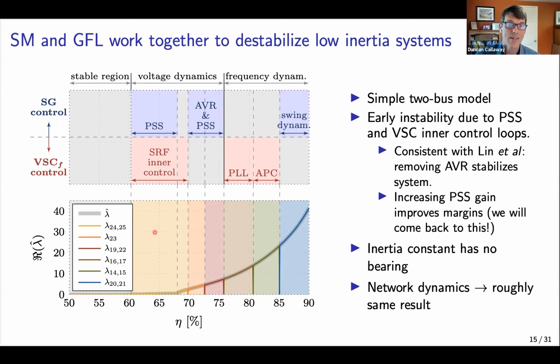What's interesting here is to ask what dynamics are implicated in this destabilization event. Looking at the largest participation factors in our instability, this is a quantitative way of saying which state variables play the biggest role as it evolves. You can see it's the power system stabilizer, which is actually trying to stabilize the system in the first place, interacting with the inner control loops on voltage and current on the voltage source converter. Those two together dominate the origination of this instability. But as we add more power electronic converter generation, other devices begin to matter as well as the initial blocks in that time scale.